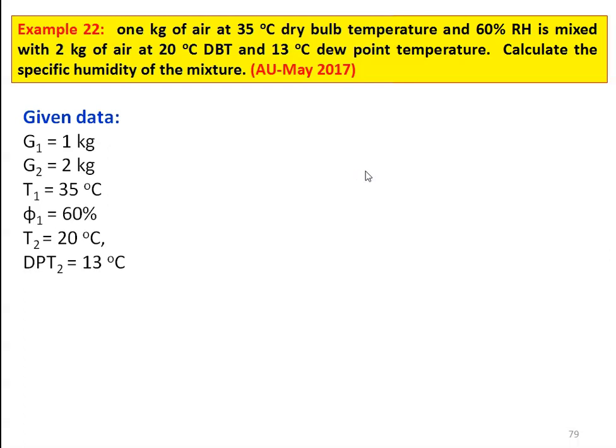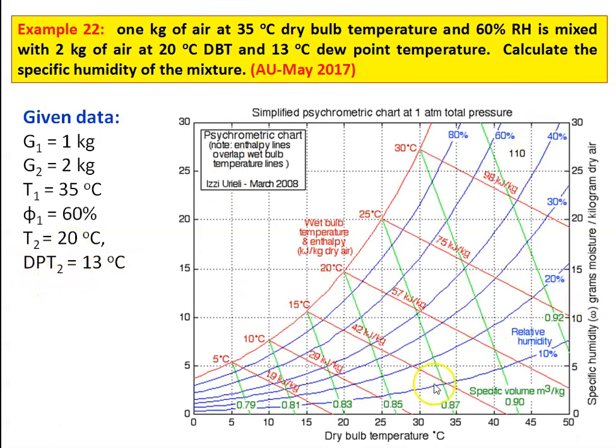We take another example: 1 kg of air at 35°C dry bulb temperature and 60 percent relative humidity is mixed with 2 kg of air at 20°C dry bulb temperature and 13°C dew point temperature. Calculate the specific humidity of the mixture. Given: G1 = 1 kg, G2 = 2 kg, T1 = 35°C, φ1 = 60%, T2 = 20°C, dew point temperature = 13°C. Take the psychrometric chart and locate the first point at 35°C and 60% relative humidity. For the dew point temperature of 13°C, you read horizontally to locate point 2.